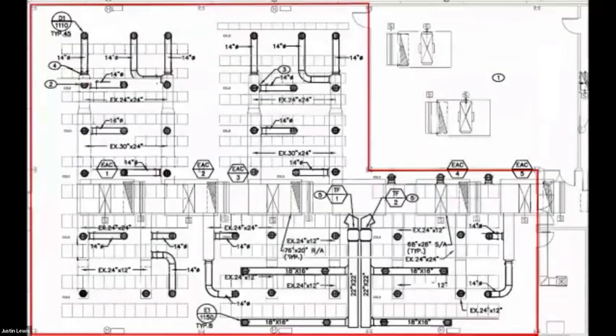We'd worked with the commissioning team previously on some projects, so they asked us to come in and do a preliminary investigation, basically find out what do they have to work with. We first installed data loggers in the cold aisles to trend the temperatures for about a week. The thermostats were found to be in poor locations for accurate reference points.